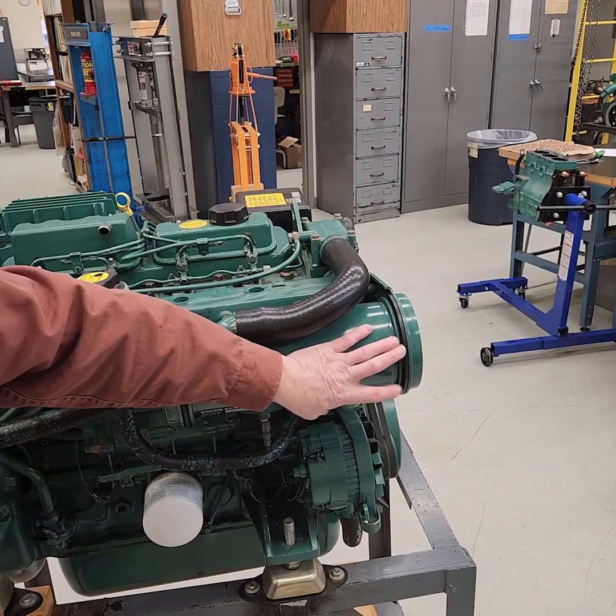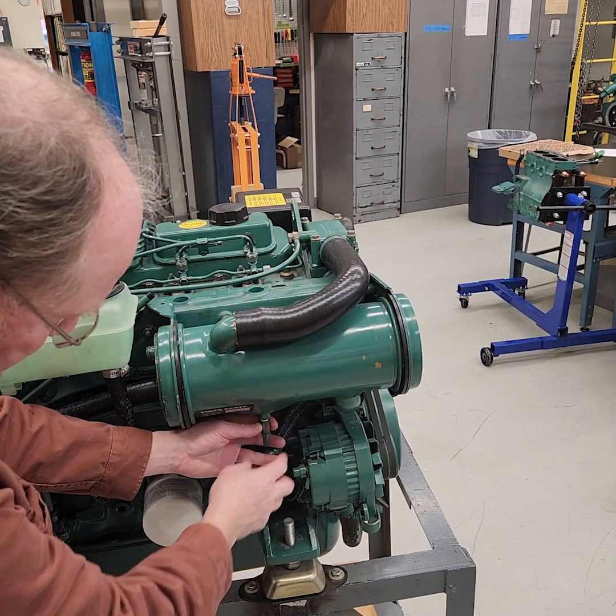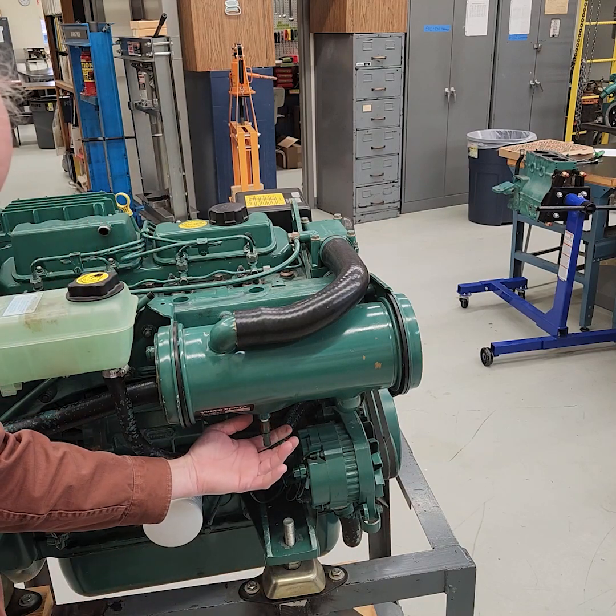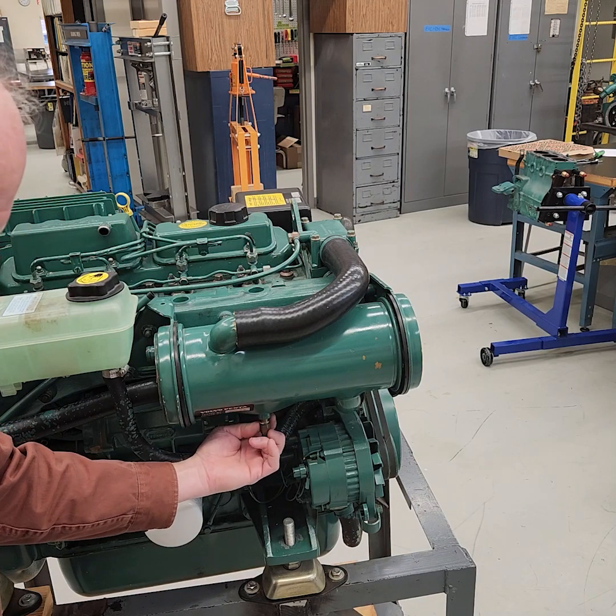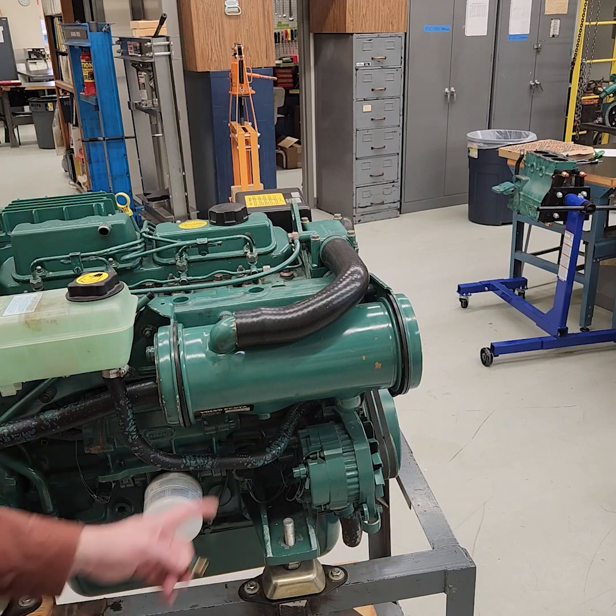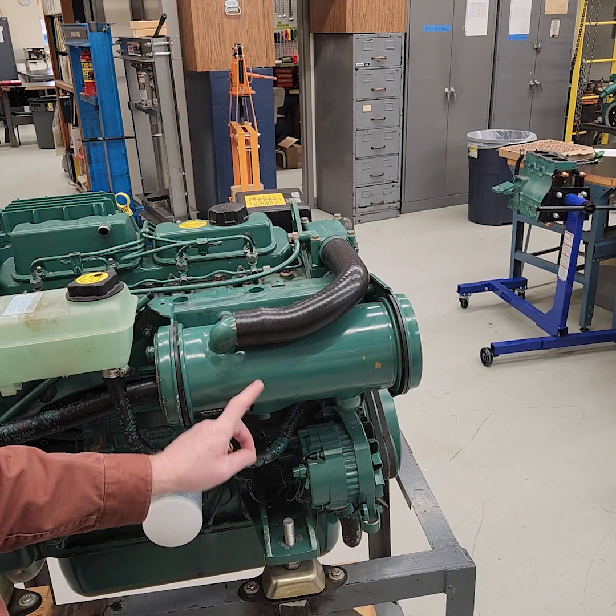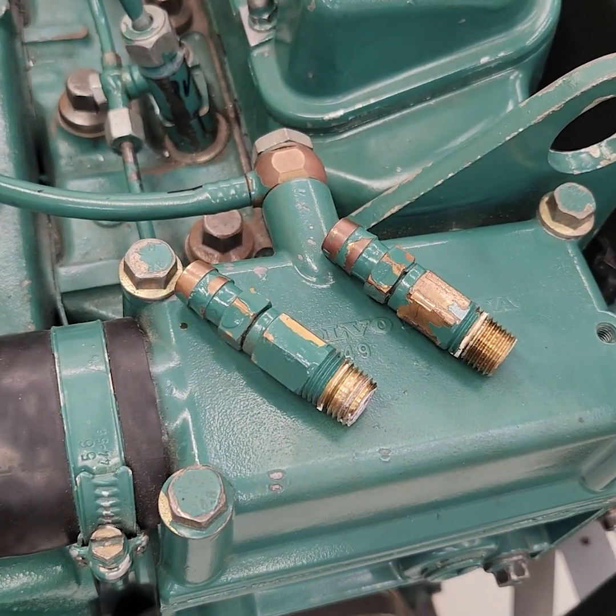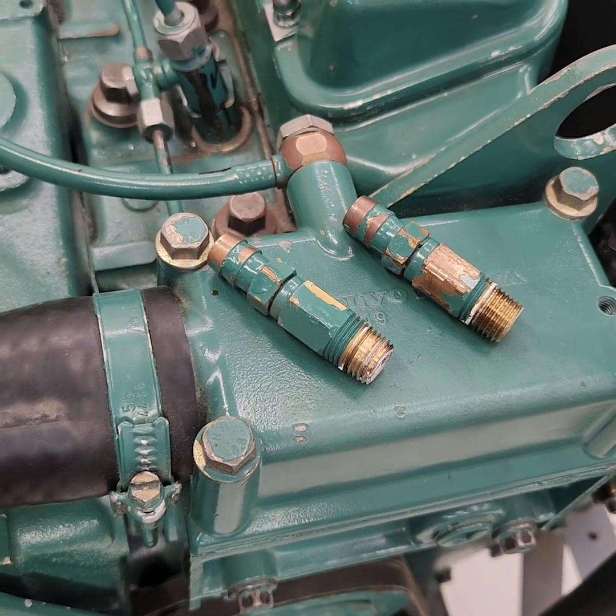Your first cooler, this is a heat exchanger, and this is a drain. So you would normally hold this fitting with a wrench and loosen this fitting, and that would drain the raw water out of it. What my recommendation is, these get replaced. So we're going to unthread these. They take a 9/16ths or 14 millimeter wrench, unthread them. That's the first one that we're going to replace.